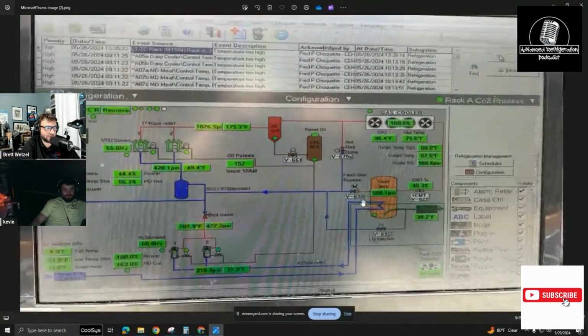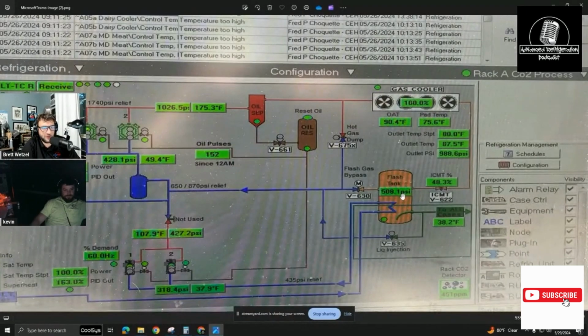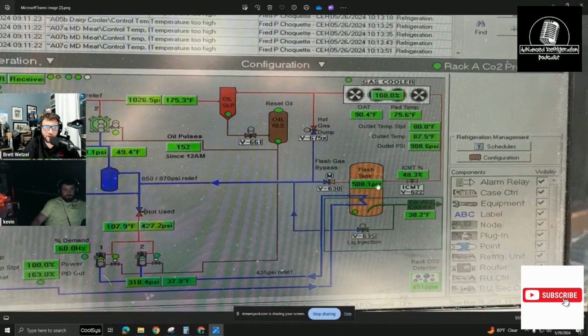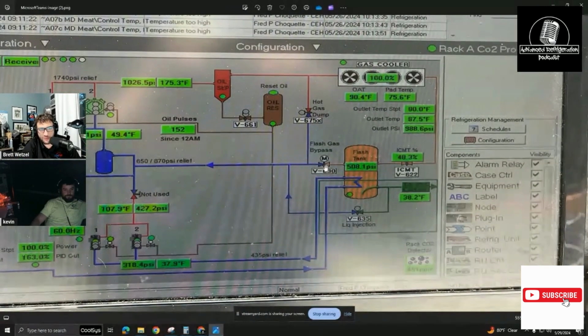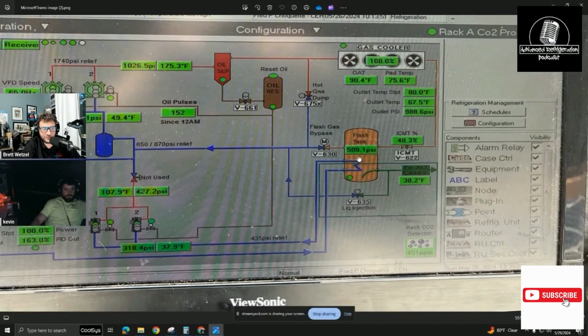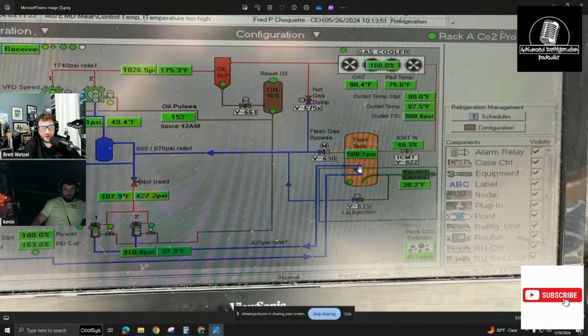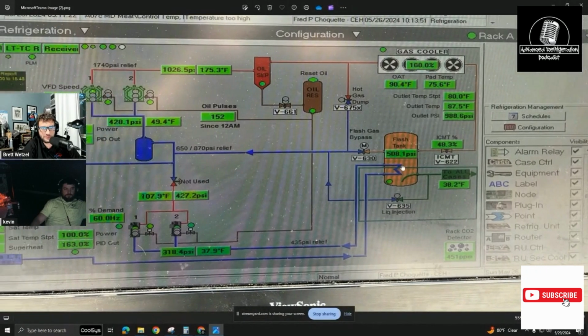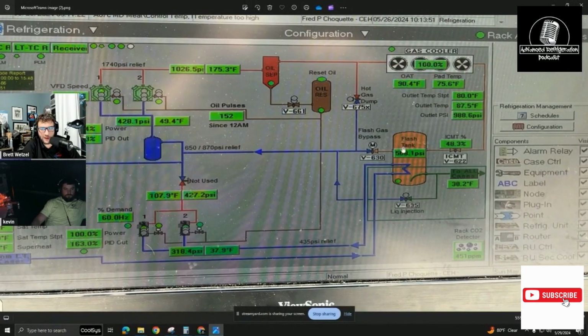The other thing I still haven't figured out, because the tech hasn't gone back, and he was there all night and getting frustrated, is that the flash tank would not stay between what the settings were supposed to be. We went through the 326 and it was set for a reference of, I think, 530. 530 or 520 PSI, I think. It's pretty high. 520, I don't remember. I think it was 38 bar. But anyway, it just wouldn't go higher than what it was.